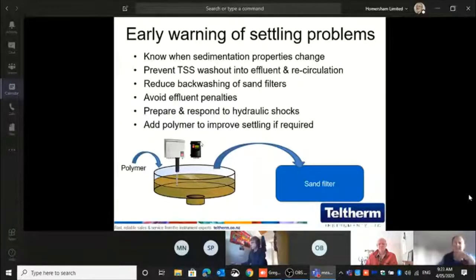The thing is, of course, early warning of settling problems. That's where these units come into play. If you got a beautiful site where you got good settlement, then anything works. You can use a sludge judge, you can use an ultrasonic, everything works. It's when problems start to happen. That's when you want to see the units actually giving you the data constantly. That's why this unit is valuable, because when things go wrong, this unit will keep giving you information.